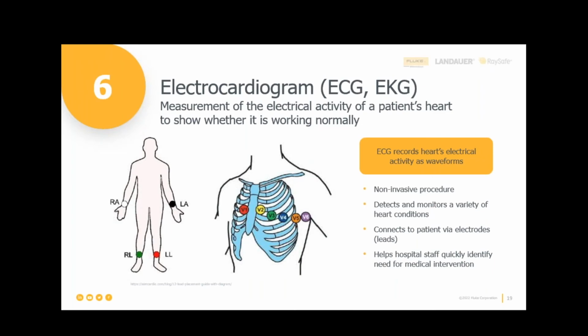Anybody else's experiences or observations about ECG? Exactly. Cables and electrodes, electrode prep, placement of the electrodes, faulty lead wires or trunk cables. Sometimes those are all built together. You can't separate them, so you would have to replace the entire trunk cable. Those are where the failures are going to happen here, by and large, more than anything else.